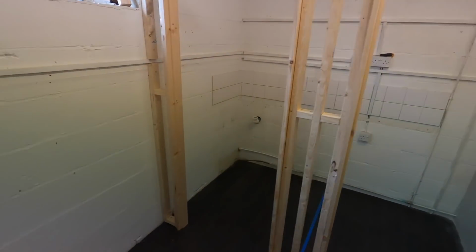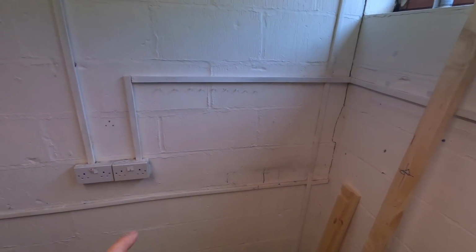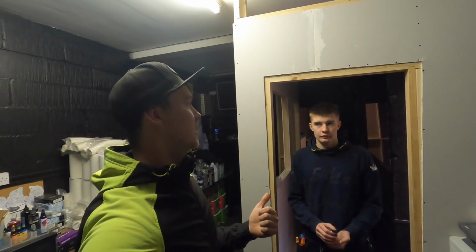One of the first jobs we've got to do, as this has obviously all been built, is this is now turned into a toilet block, which was the old kitchen. So we're removing all the sockets that pass through, but we've got to get rid of these. We're going to put a few spurs here for the water heater, but then we've got to rejig it where we take it out, because the ring runs all the way through here. So find out, isolate it. We've got to the fuse board. The fuse board's not labelled. We don't know what anything is. I've got the socket tester, so we're just going to do a bit of shouting backwards and forwards to figure out what's off. Yep. Then test if it's a ring to start with.